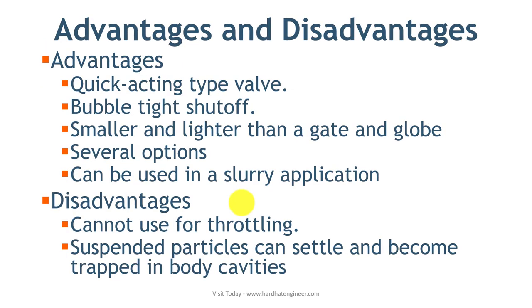Here you can see the advantages and disadvantages of using a ball valve. The ball valve is a quick-acting valve that offers bubble-tight shutoff. It is smaller and lighter than a gate and globe valve of the same size. Several multiport design options offer flexibility to choose the best valve for your service. The ball valve can also be used in slurry applications. On the disadvantage side, the ball valve is not designed for throttling — regular throttling can damage the ball. If there is a problem with the seat, suspended particles can settle and become trapped in the body cavities, causing wear, leakage, or valve failure.